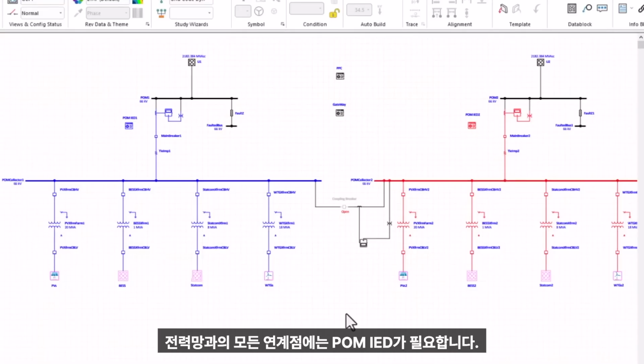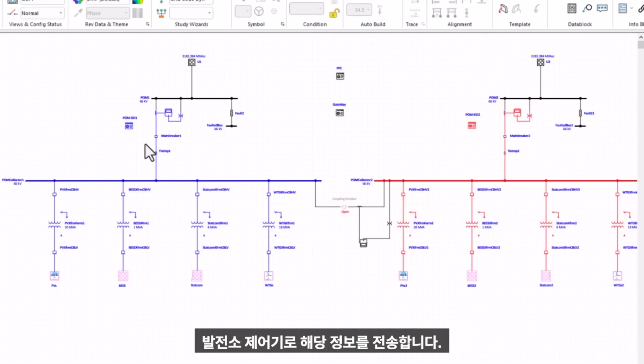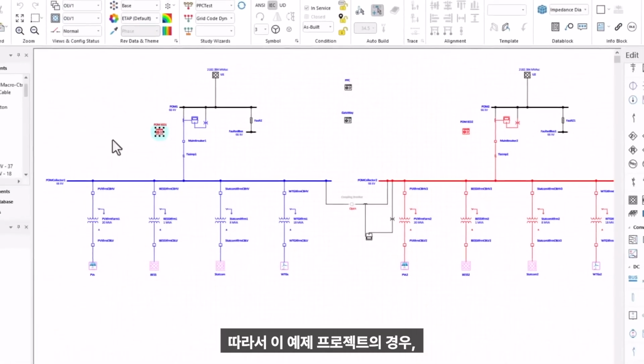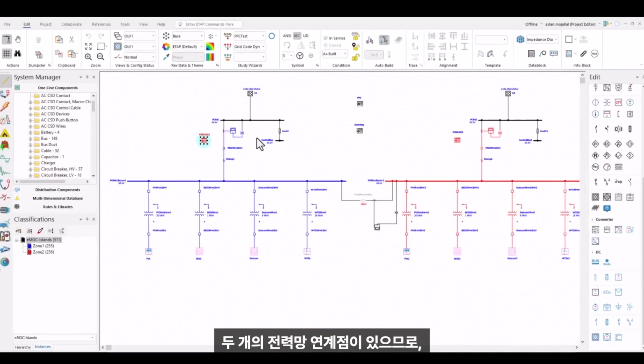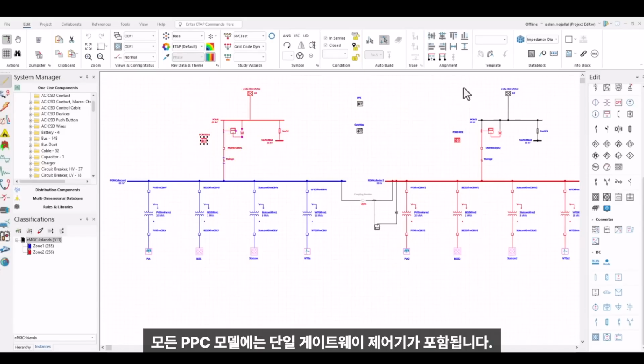For every point of interconnection to the grid, we also need a POM IED. This device serves as the meter at the interconnection point, measuring active power, reactive power, voltage, and frequency, and then sending the information to the power plant controller. So in this example project, since we have two utility interconnection points, we also have two POM IEDs. And in addition to those devices, every PPC model includes a single gateway controller.